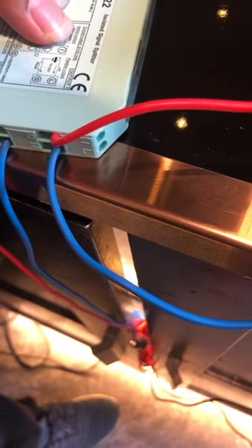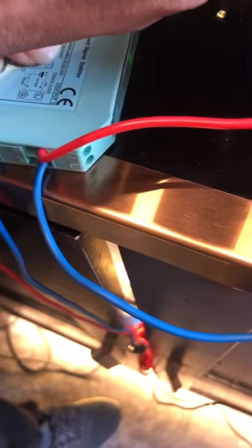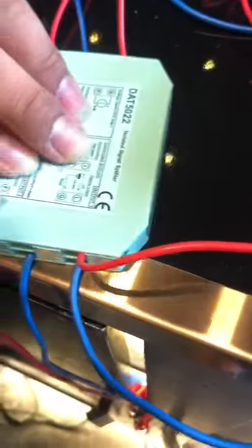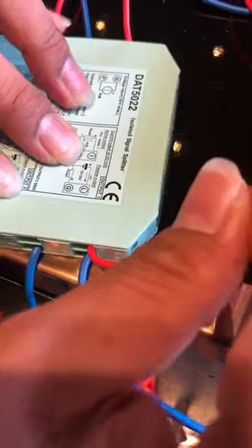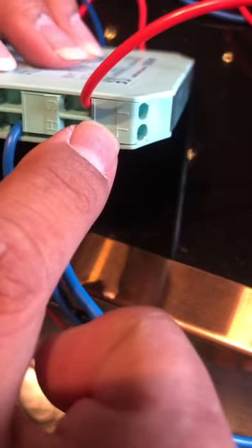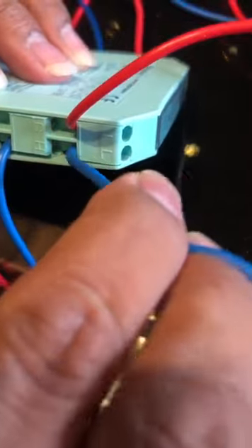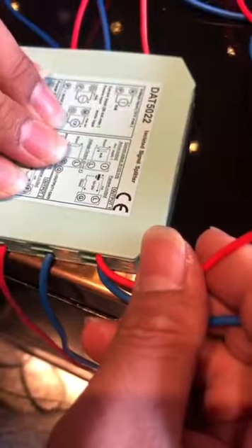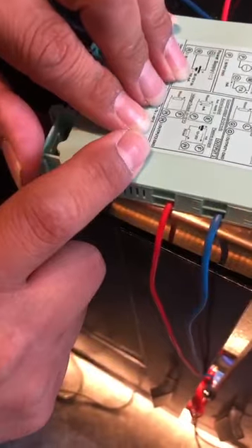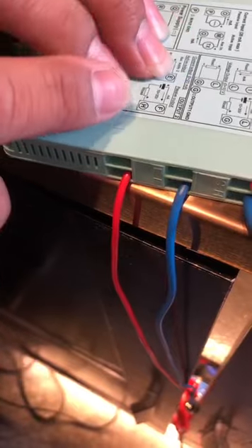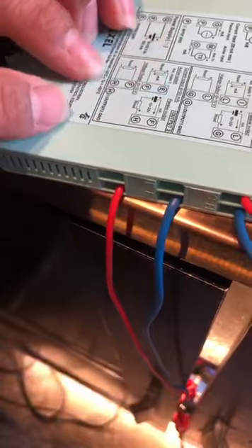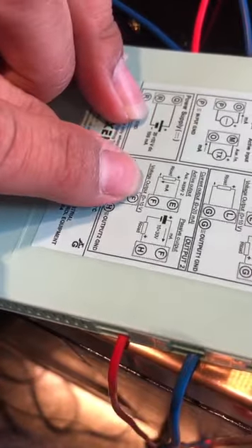And then on the output, very important, we are using active output, since we are connecting directly to the meter. So for active output, I should be plus. You can see from here there is a letter designation. So I should be connected to the plus, and then you can see from here again L should be connected to the minus. This is output number 1, set as 4 to 20 milliamps. Output number 2 is set as 0 to 10 VDC. We can see from here that we are connecting for 0 to 10 VDC. You should see this diagram here.